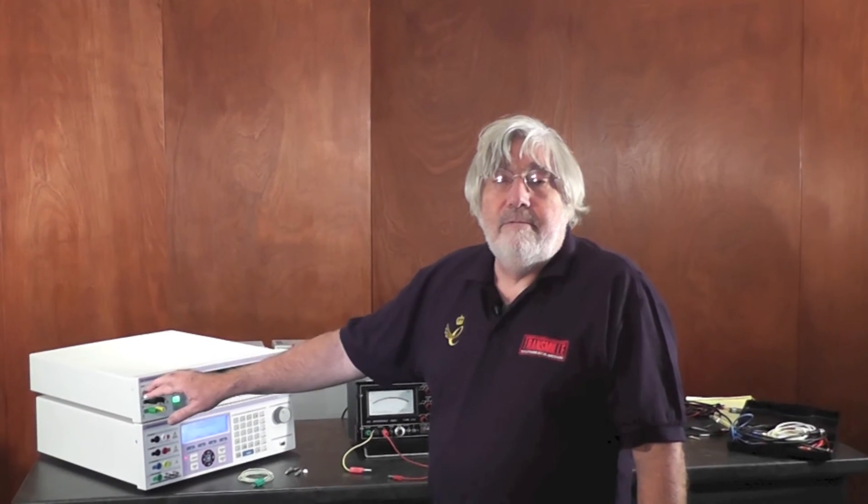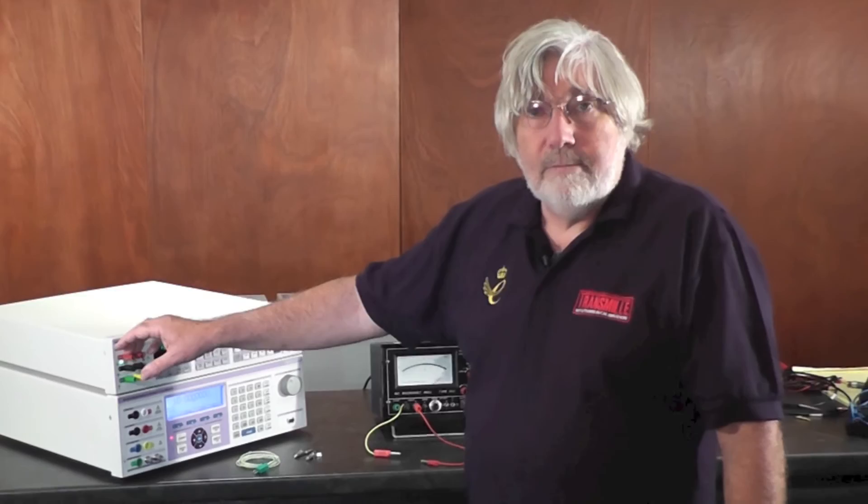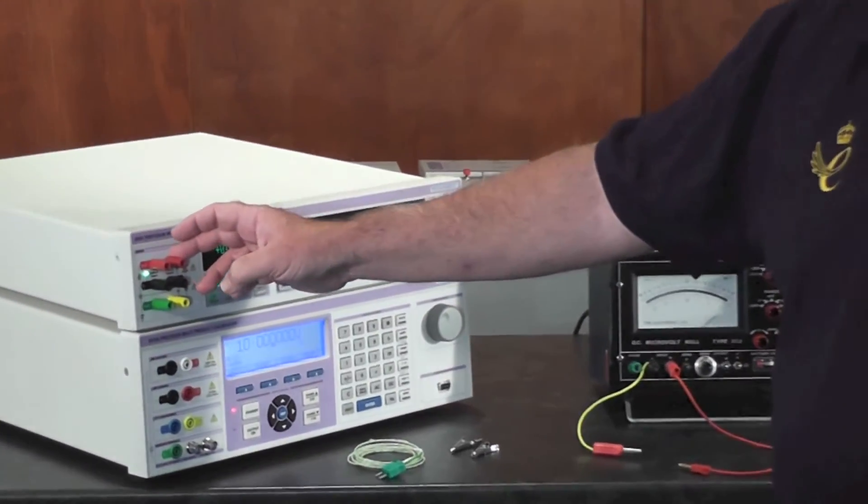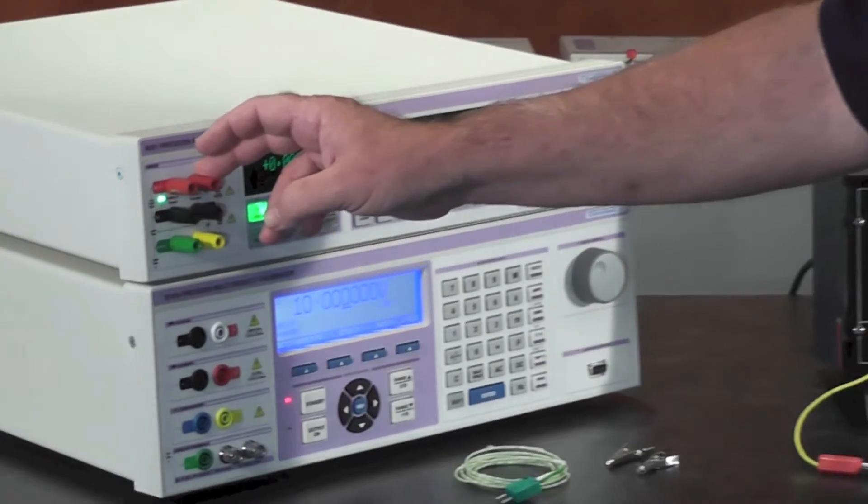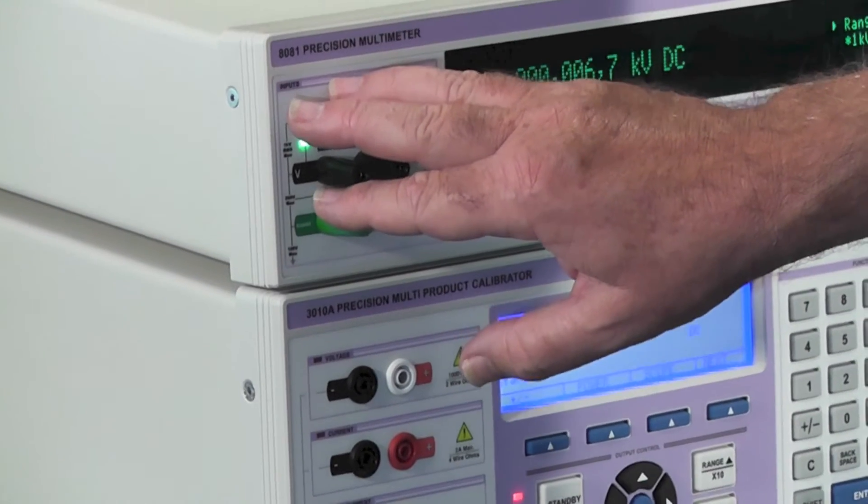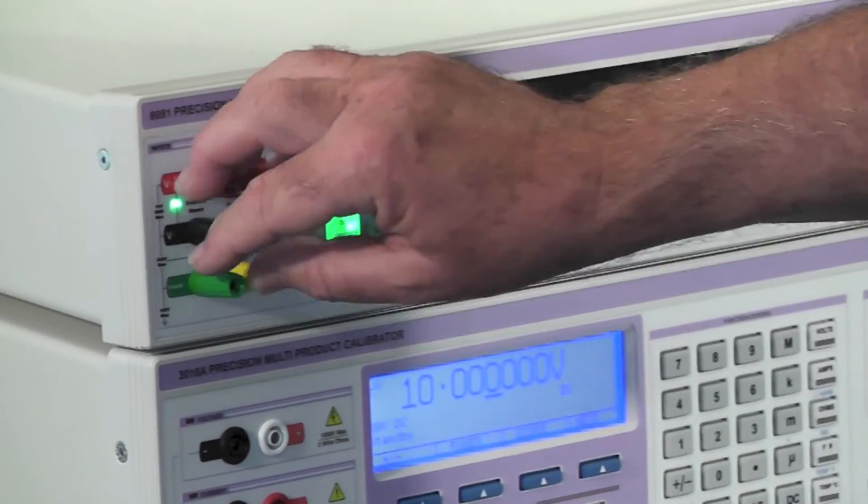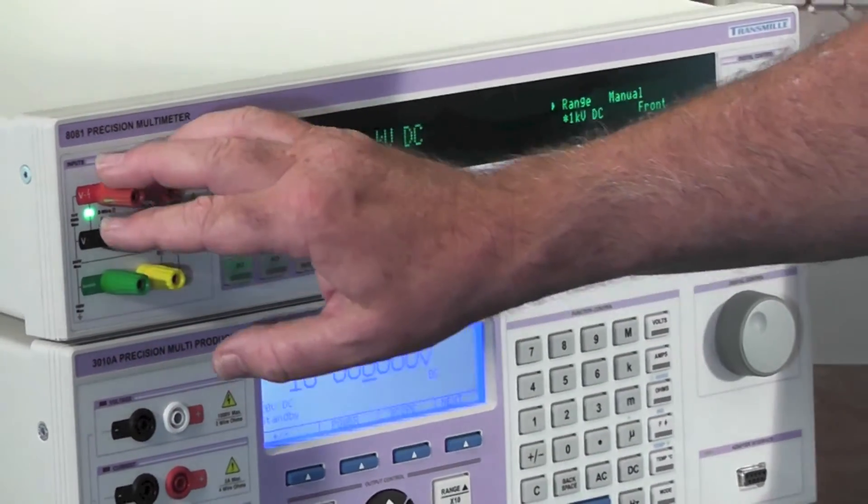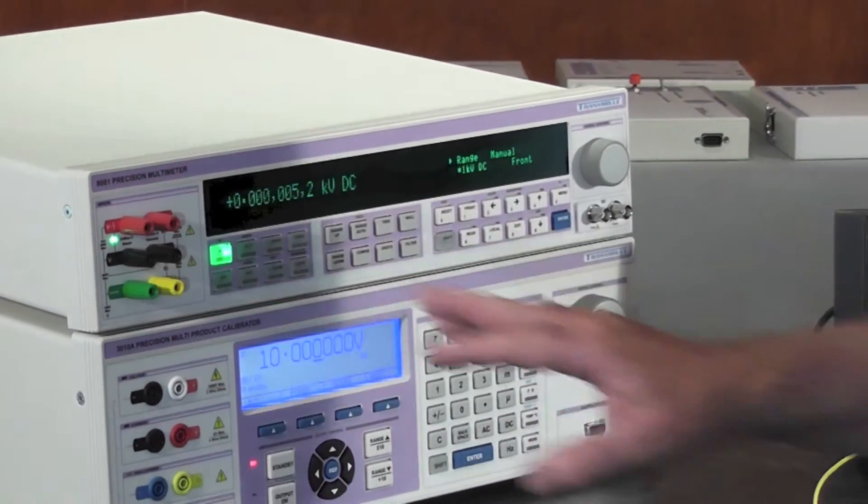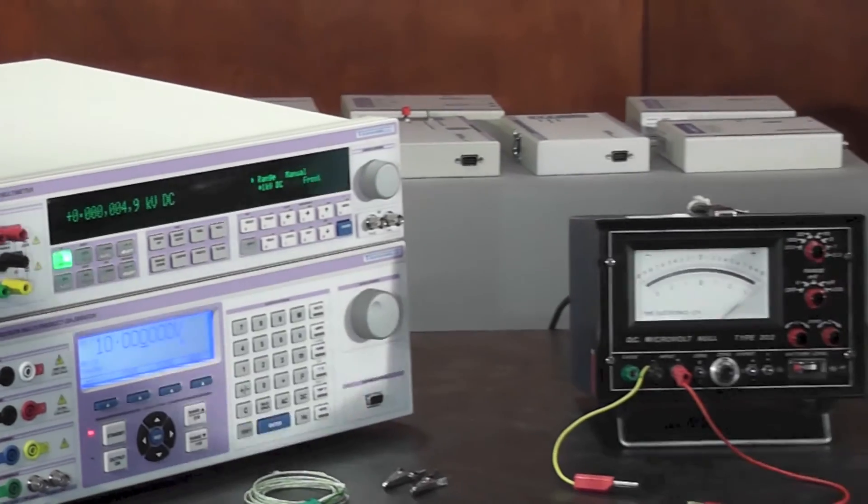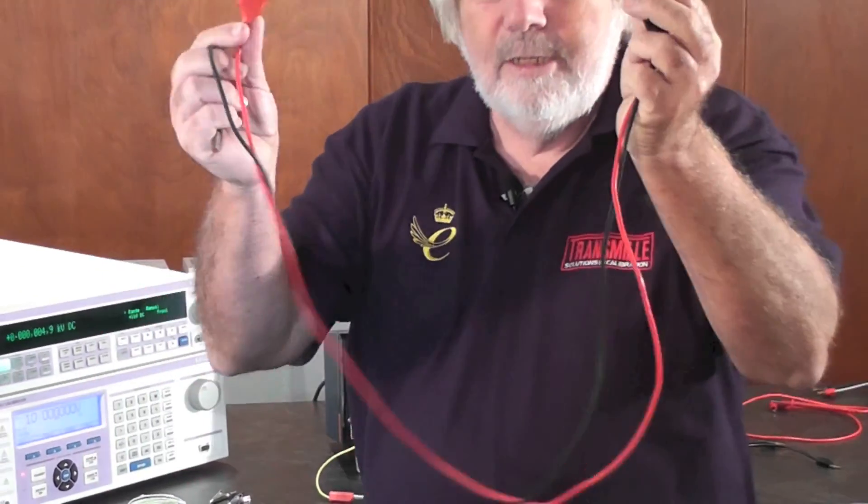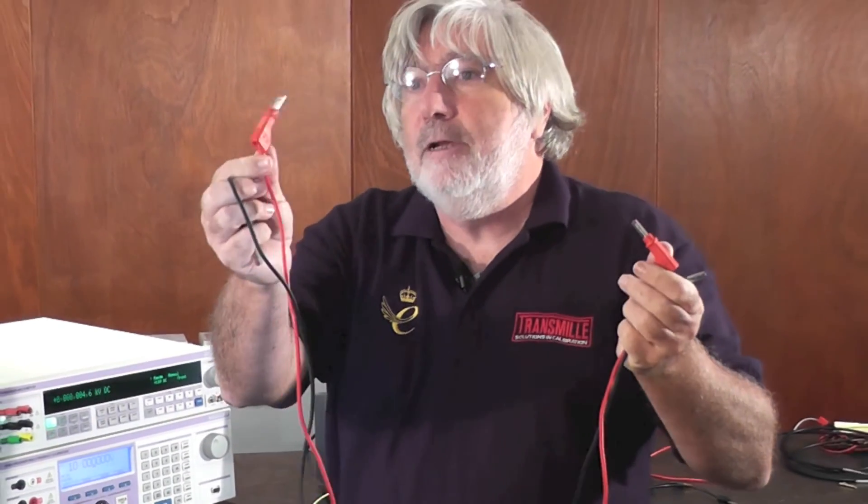All of the precision manufacturers, their instruments will have on them low thermal, usually copper or deoxygenated copper connections which are almost always gold plated. So whether you're looking at a precision calibrator or a precision multimeter, the terminals here will be good quality copper gold plated.